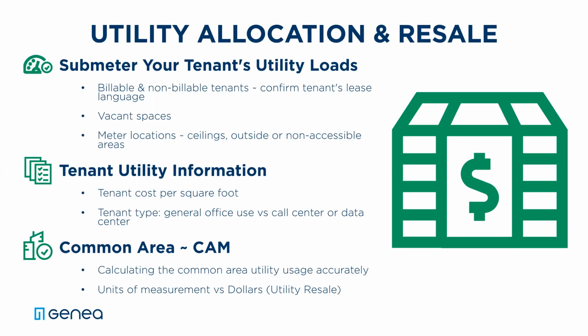And meter location, when you're installing your meters, is an important aspect. Lots of times we'll go in for water meter readings and we've discovered that they're 10 to 12 feet up in the ceiling and not accessible, to where they have to then, if it's not a remote read, install a remote read down so the meter can be read manually. And accessible areas, it's important to install the meters in accessible locations. Even if your meters are being read remotely, if you need to service the meters for any reason, they need to be accessible.